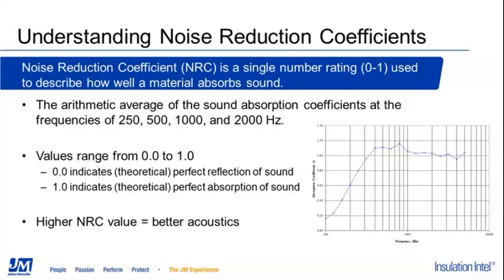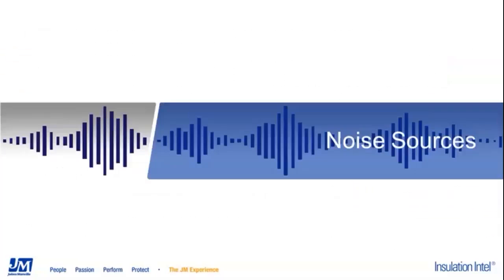Additionally, in mechanical rooms, it can be beneficial to treat the exposed surfaces, which could be walls and ceilings, even possibly the sides of equipment, with absorptive material to reduce the amount of buildup in a space, which equates to less sound being able to transmit through walls or floors into adjacent noise-sensitive spaces. Additionally, duct lining is fairly inexpensive and can be used in other applications, including theaters, where a black unwrapped butt-faced material can improve the sound quality of a room at a low cost. So hopefully that builds a good base of what we're trying to meet.